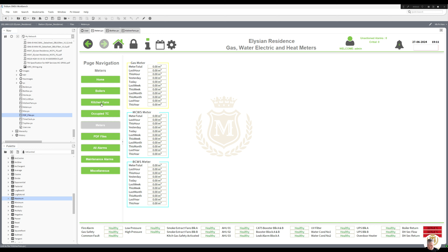Leave that as it is. It's mainly for the maintenance people, but it gives me some idea. When I'm on site, I can just go straight to PDF files, see the mode I need, which is the stage mode, that's jumper 1, and we'll be using jumper 2, 0 to 10 volts. Meters occupied, kitchen fans done, boilers. I keep putting this off, but might as well finish it since it's only the boilers left to do.